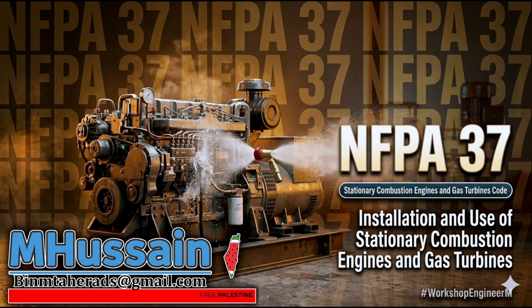But why 20 minutes? Why can't the gas just put the fire out in 1 minute and we're good? Thermal inertia. A heavy diesel engine block and a 900-degree exhaust manifold hold massive amounts of stored heat. Oh, I see. If the gas leaks out after 5 minutes, fresh oxygen rushes back in. The exhaust is still at 700 degrees. The fuel is still on the floor. Boom. Instant reignition. Exactly. The temperature is still above auto ignition, and now your suppression gas is gone. You have a free-burning fire.